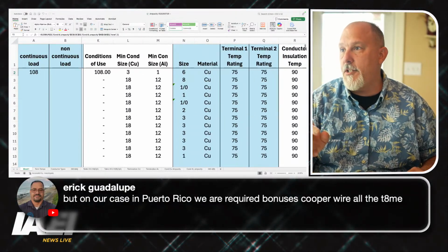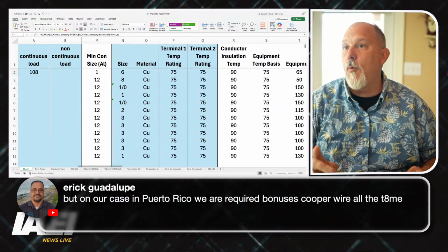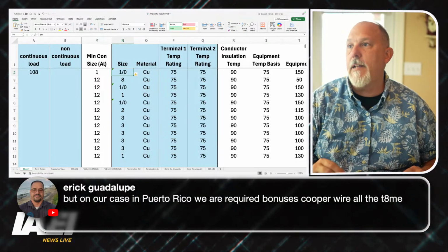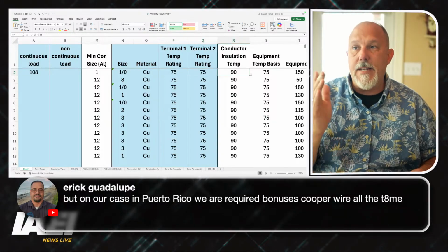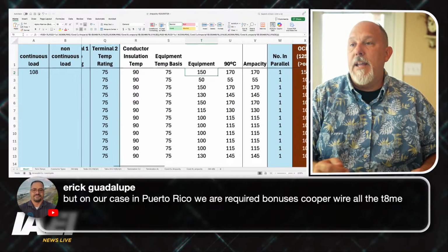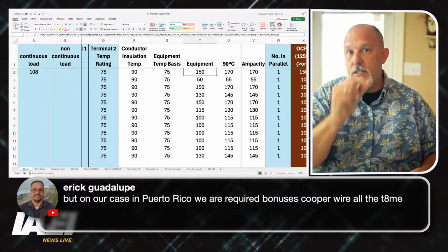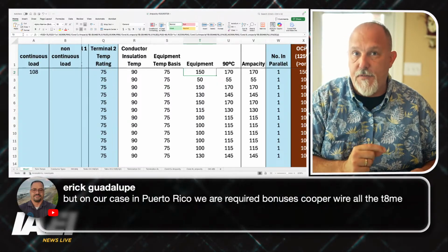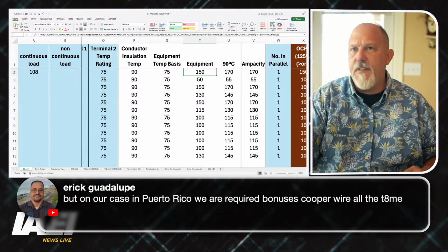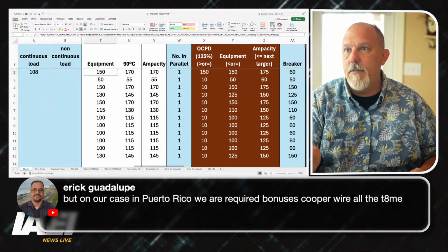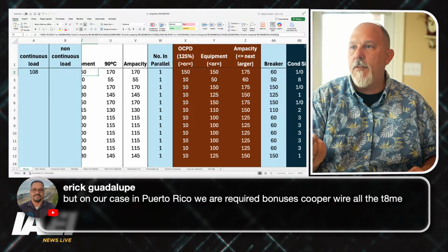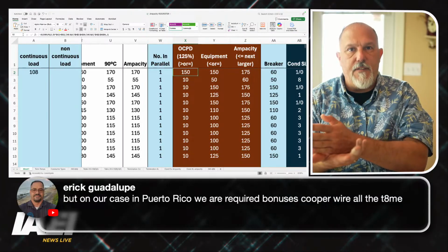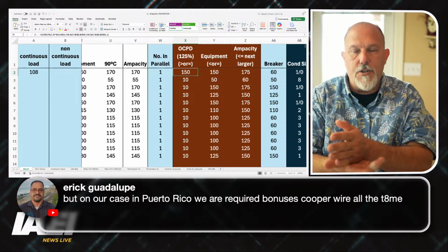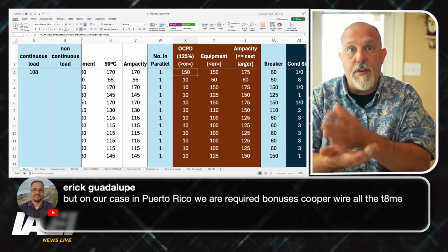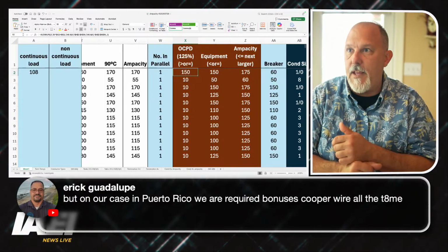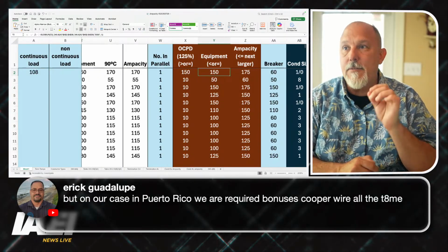So for this case for copper, we're going to pick a 1-aught conductor. So I'm going to come here and pick my 1-aught copper conductor. There's my temperature rating, 75. There's my insulation rating, 90 degrees. For my equipment, based upon a 110.14 requirement, my overcurrent protective device can't exceed 150 amps. I have 135 amps of continuous load. I can't be less than that. So 125% must be met by a 150 amp breaker, because I don't have a breaker at 135 amps. My next largest overcurrent device for the 135 amps of continuous current, because I can't go less, is 150 amps.